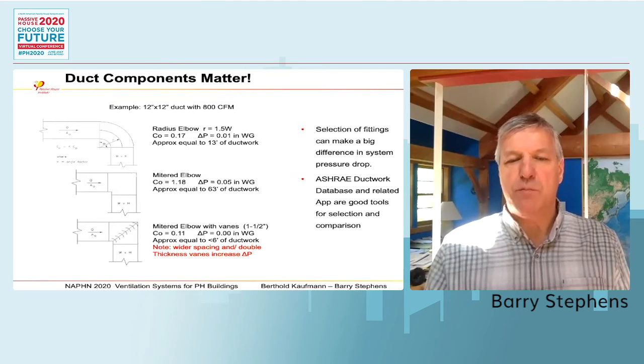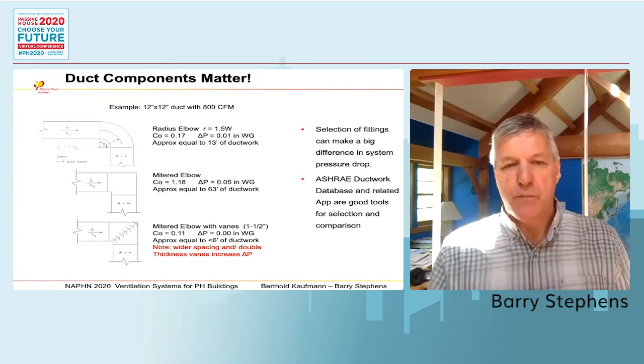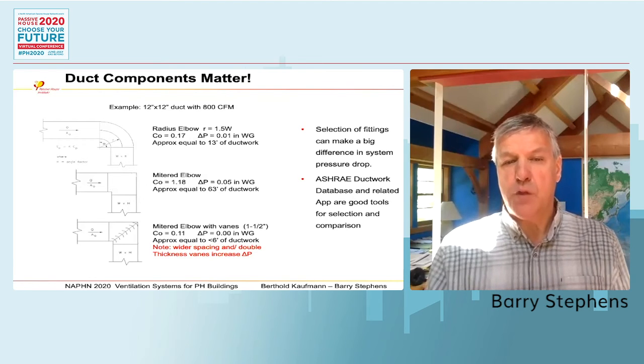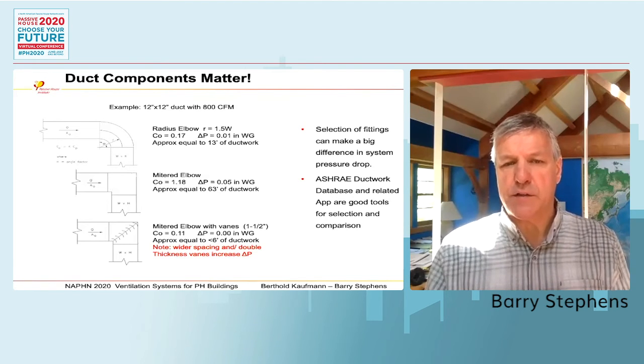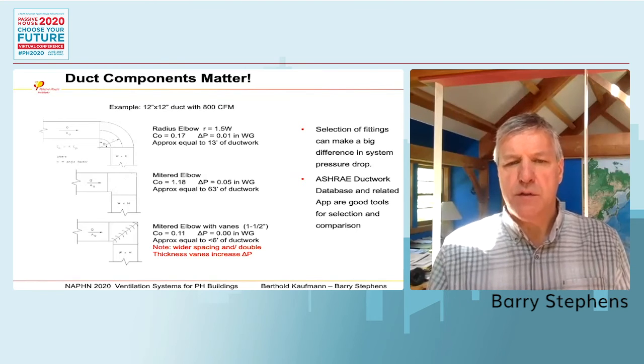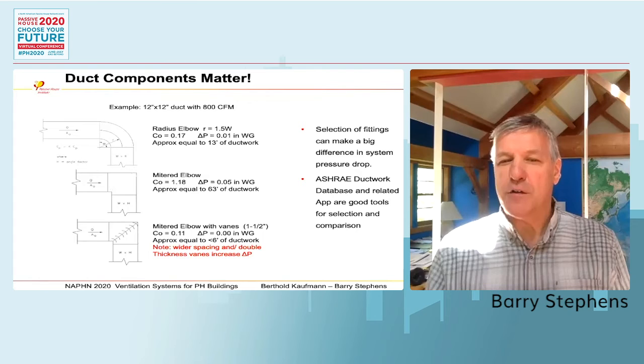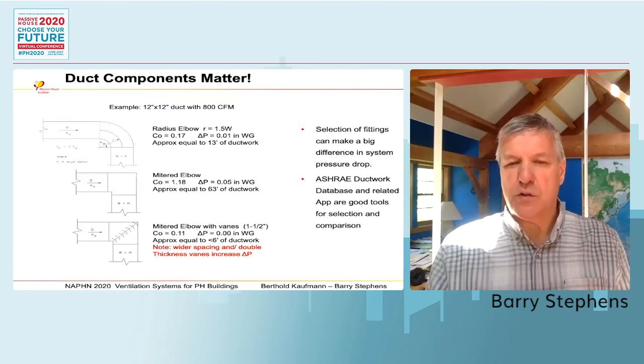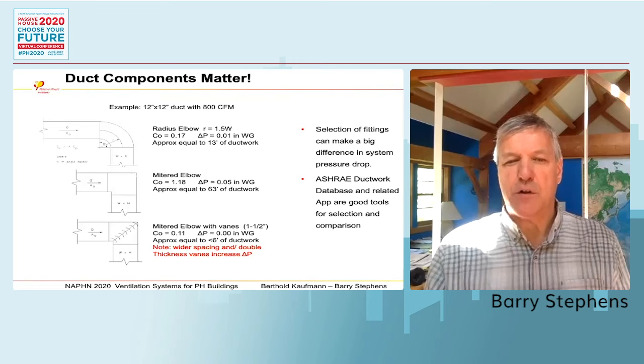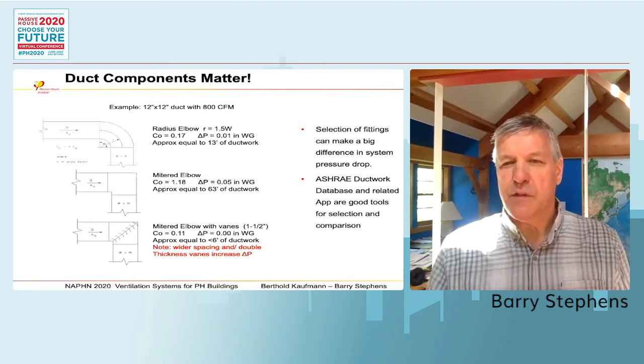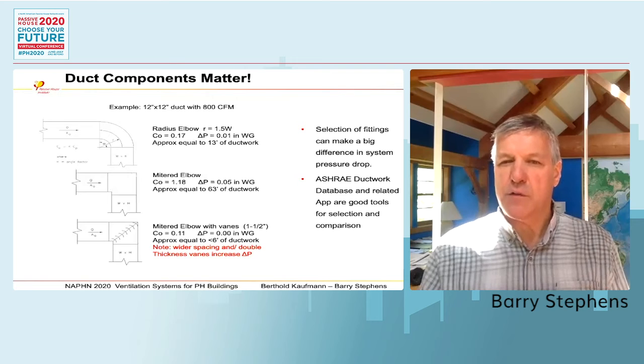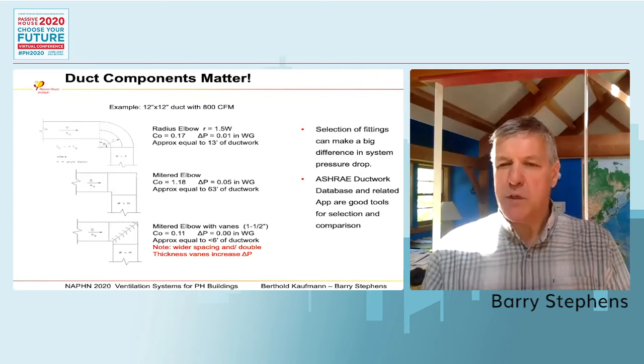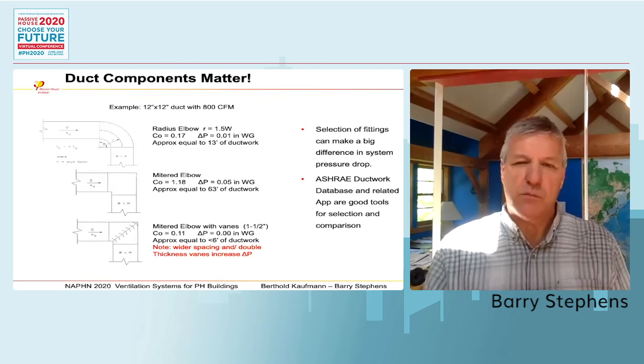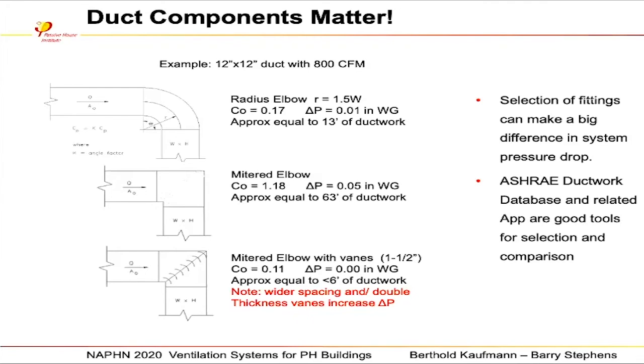So what this means is you add that all up. If you have 20 of those elbows in your system, multiply 20 times whatever that equivalent is. So if you're multiplying 20 times 63 feet, that's over 1,200 feet of ductwork, as opposed to 120 feet of ductwork if you use the turning vanes. And what this translates into is a very significant difference in the static pressure, and what that means is you're going to use less power to move your fans to move the air through the system. So these pieces and parts really add up, and it's really something to take into account.